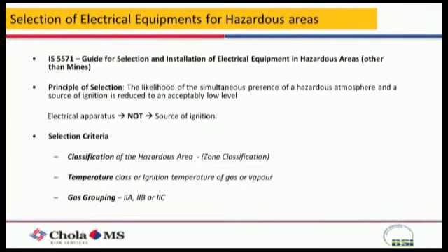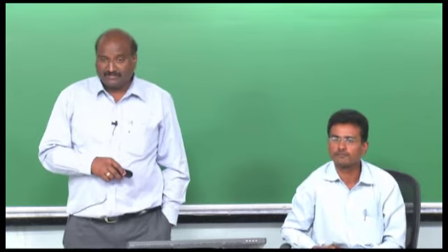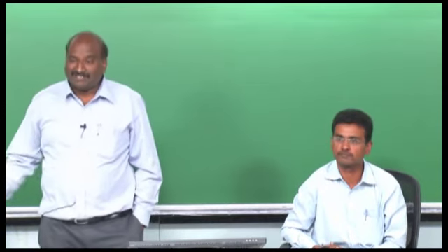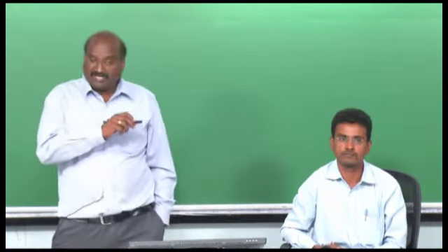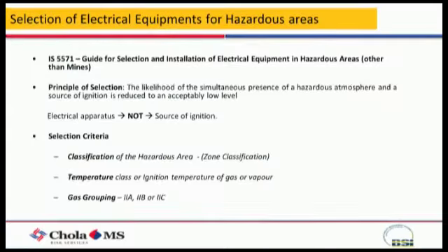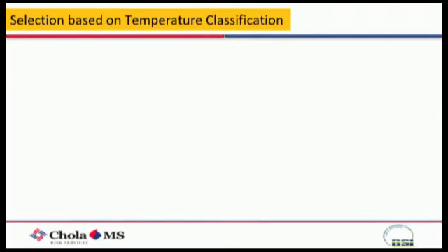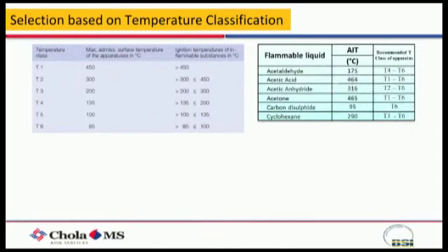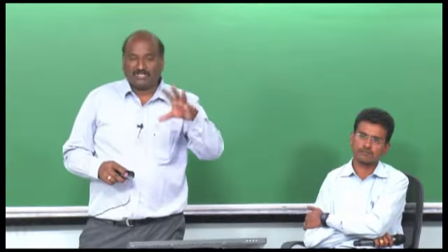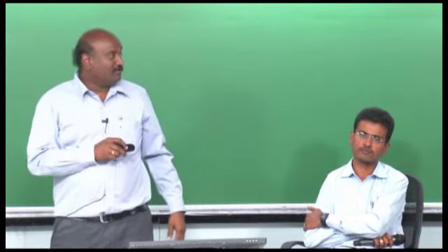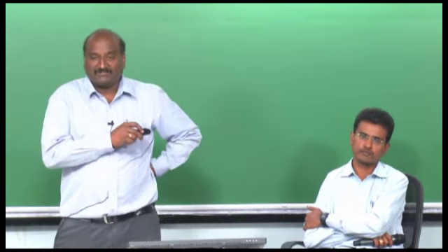The selection of electrical equipment in hazardous areas, other than mines, is dealt with in Indian Standard 5571. Selection criteria will depend upon hazardous area zone, temperature class, and gas group. All these parameters are available on the name plate. By reading the name plate, you will be able to understand whether this motor can be used in which application and which location. You need to look at the name plate for T classification — the temperature class.